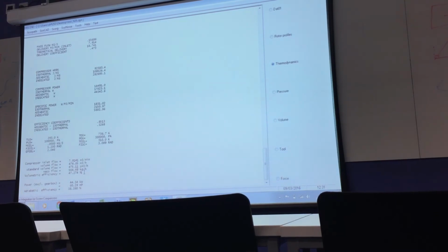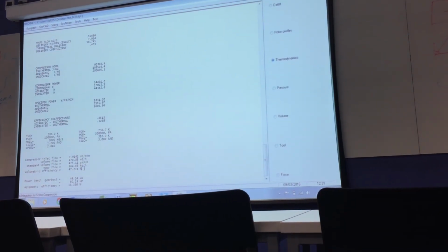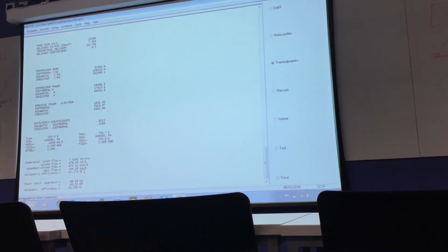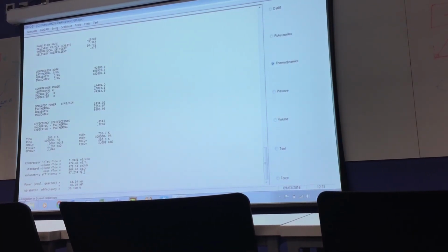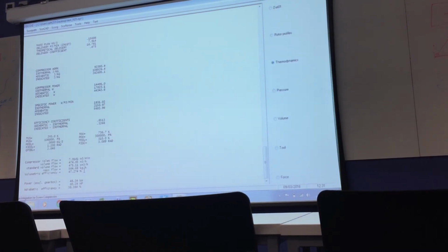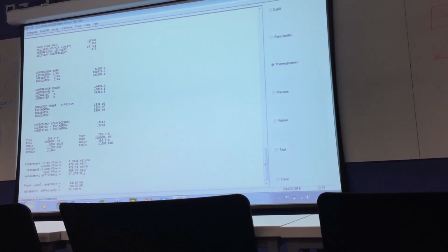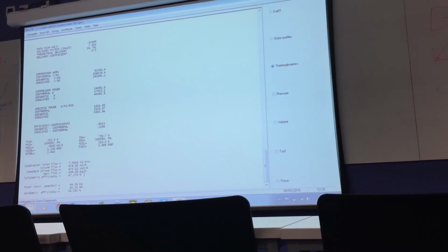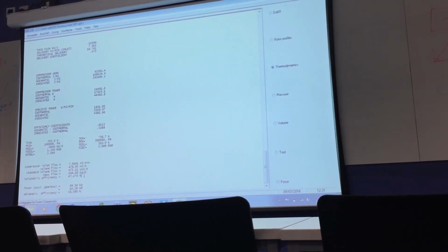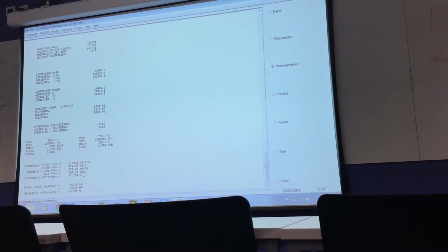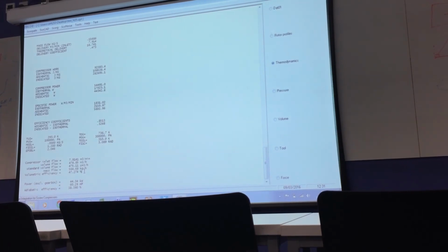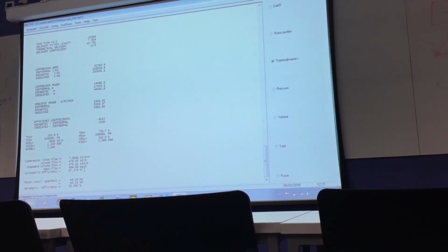So you'll have to study these gaps independently. Keep in mind that change only one parameter at a time, otherwise it will be very confusing to understand what is going on. Let's say you are studying the gap, then keep everything same, pressure conditions, operating speed, and just give steps increment to that gap and see what is happening to the results. In results, you can check efficiencies, power, and flow. Just investigate volumetric and adiabatic efficiency, specific power, and mass flow. And try to see how each of these parameters are influencing the three. Okay.